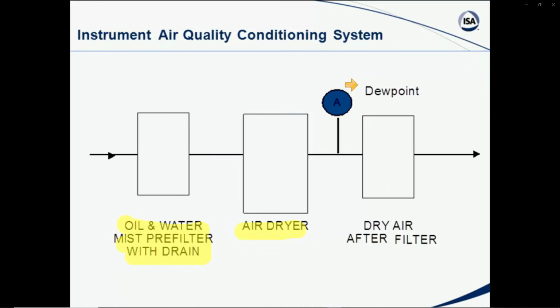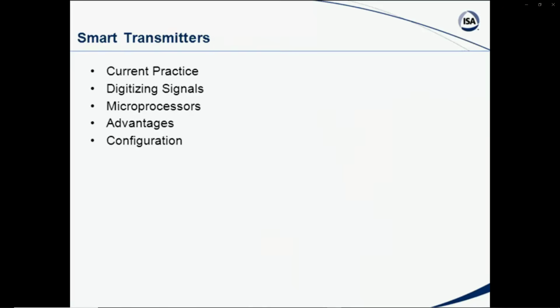maybe we would check the dew point, and then even after that, there may be some sort of an after filter installed to ensure that we do have good instrument air quality, that the air we're using for our pneumatic devices, be they transmitters, controllers, or valves, will be the type that we would want to have working in our particular plant. Probably this instrument air system will be distributed at anywhere from 35 to 50 psi. Many facilities have a plant air system and then a separate instrument air system that they can take advantage of and that they use as far as their operations are concerned.